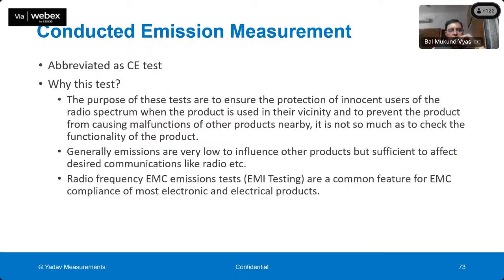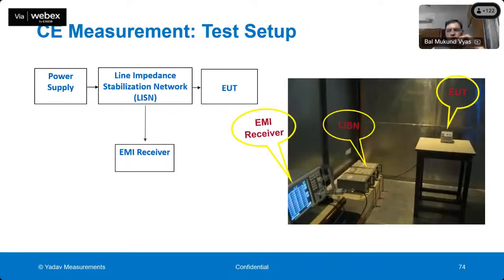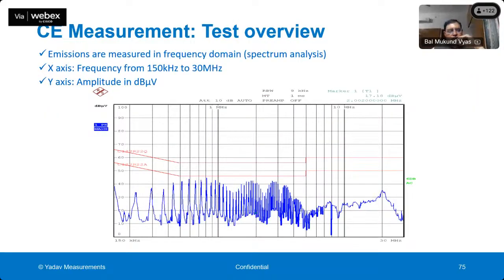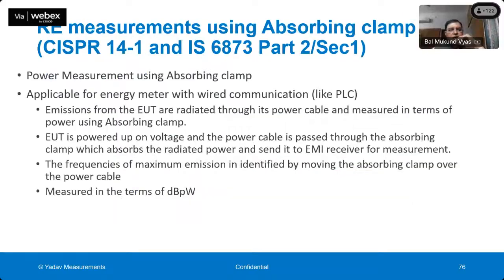Similarly, you have to carry out conducted emission measurement. That is, conducted emission measurement is how much the meter is emitting in the cables. So you can see here the picture for measuring this type of conducted emission. You need a line impedance stabilization network, and the meter is connected with the cable, and that cable is connected to the EMI receiver. So this EMI receiver is measuring how much radio frequency the meter is emitting in these cables. This ensures that the meter is not disturbing the devices which you are using in your house. So this is a typical graph, starting from 150 kilohertz to 30 megahertz, of how much the meter is emitting. So this kind of measurements are there.